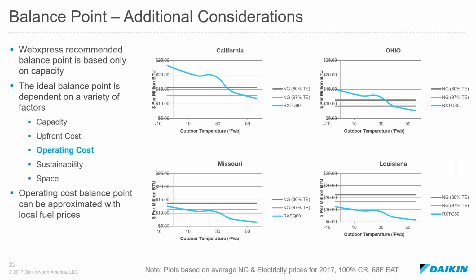So up until now, we've just been talking about balance point in respect to capacity. So what physically can the system do before it runs out of capacity and we have to switch over to a supplemental source, or switch part of the system over to a supplemental source, so we have the capacity available to other zones who don't have a supplemental source. But there's really a number of factors that come into play as far as balance point. Capacity is just one of them. The other most significant one would be operating costs. So what makes sense from a cost of fuel standpoint to run? Does it make more sense to run electricity or natural gas, which is going to cost me more? That's going to be dependent on a lot of things, primarily your local fuel costs.